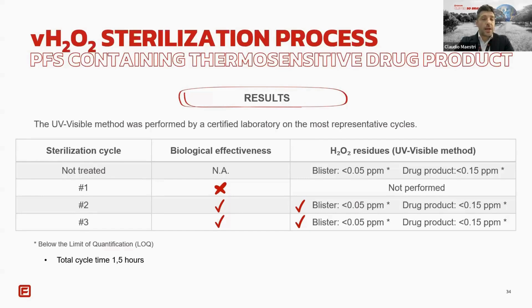These case studies highlight an important point. Developing an effective sterilization process is not about replacing one method with another one. It's about tailoring the process to the product by controlling injection, deep vacuum pulses, and aeration. In this way we can design H2O2 cycles that achieve sterility assurance while minimizing residue and protecting material compatibility.